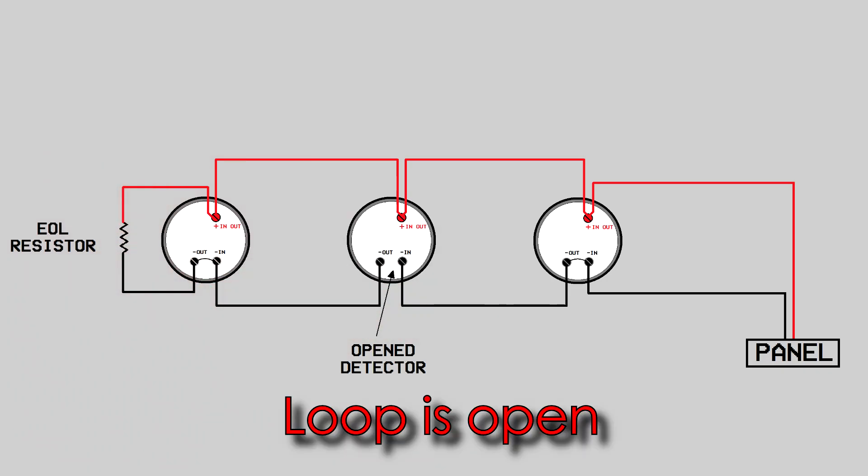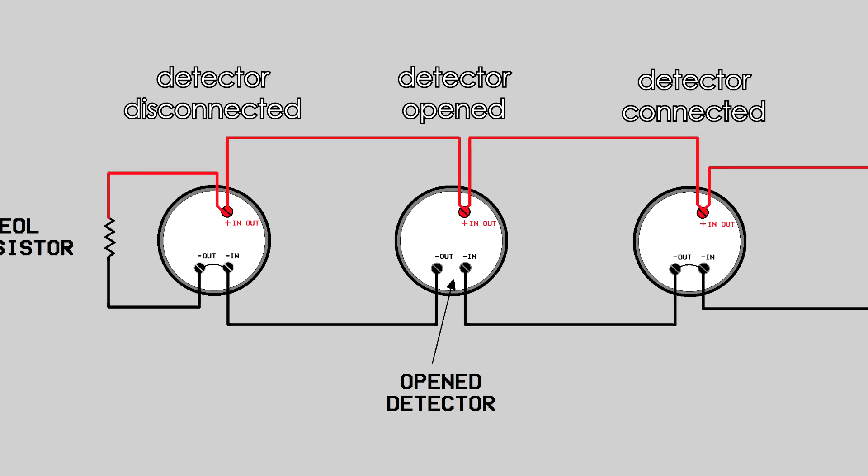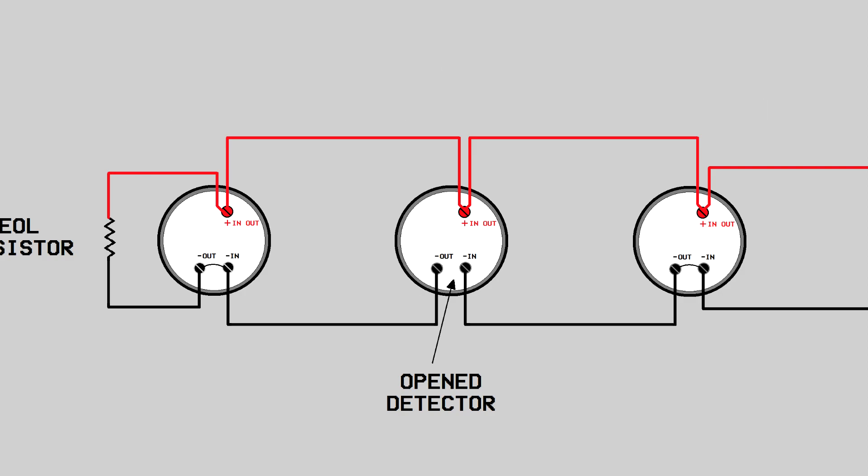The minute any detector is opened, the circuit path of the EOL resistor is opened. Therefore, the panel detects that some detectors in the line may not be actually connected with the system. The negative in and negative out terminals are shorted together inside the smoke detector unit. So whenever the detector is opened, the EOL path is opened and the panel gets to know about it.